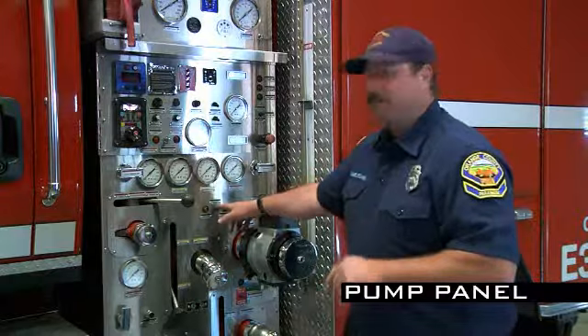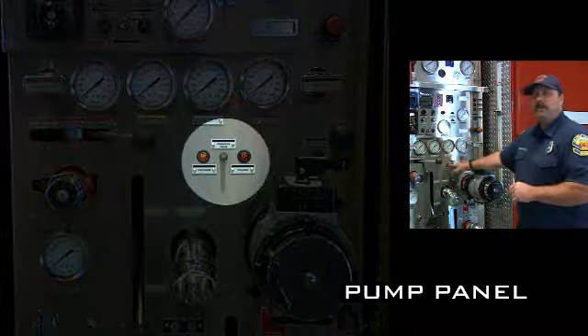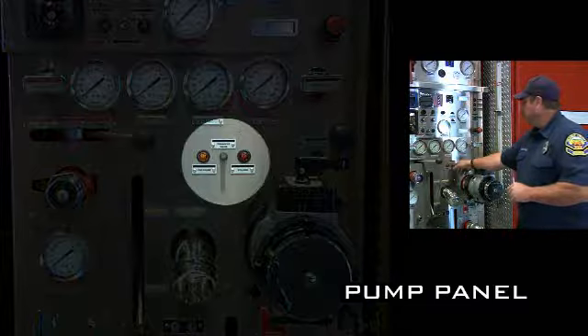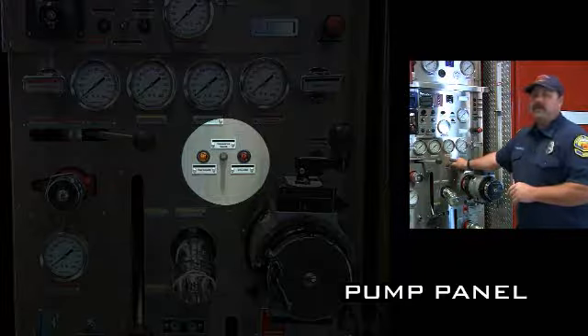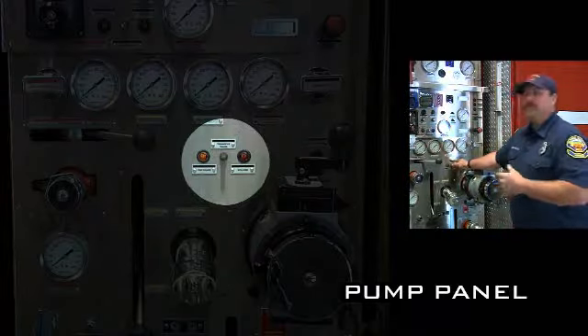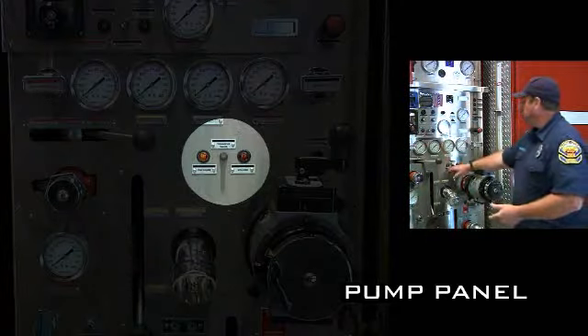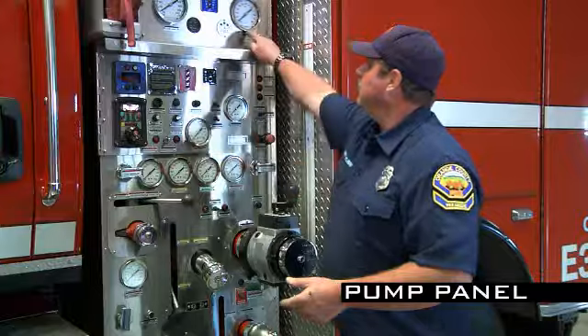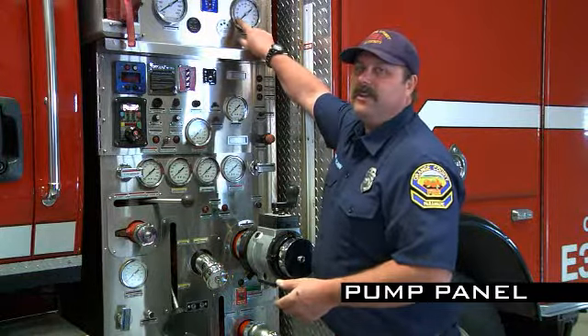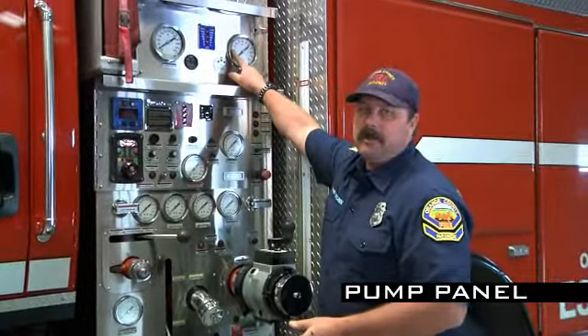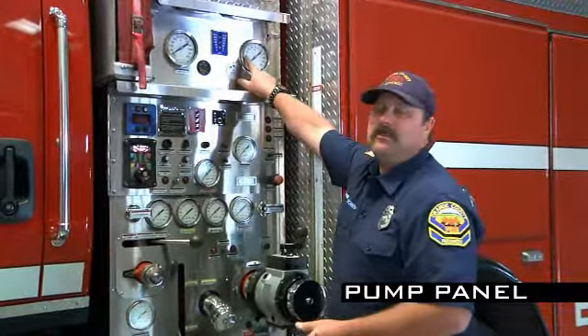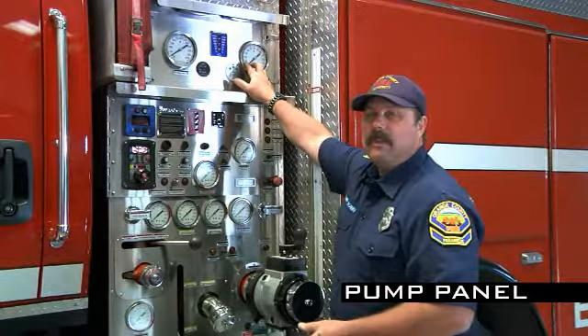Another issue that we have with our Westmarks is the transfer valve. Okay, it's labeled pressure and volume. This is a 2-stage pump, 500 GPM. We tend to run these pumps in the pressure mode, but these need to be exercised. The shop would prefer daily, at bare minimum weekly, multiple times with water flowing. So start the truck, start the pump up, and move these transfer valves appropriately to prevent damage and make sure that they move, okay? From pressure to volume. On occasion, these lights may or may not light up, but you can see on the pressure discharge, if you're in volume, it tends to be at about 50 at idle. If you're in pressure, it tends to be around 100 at idle. Okay, so if you're in pressure mode, expect to see about 100 PSI at idle. If you're in volume mode, tend to see about 50.